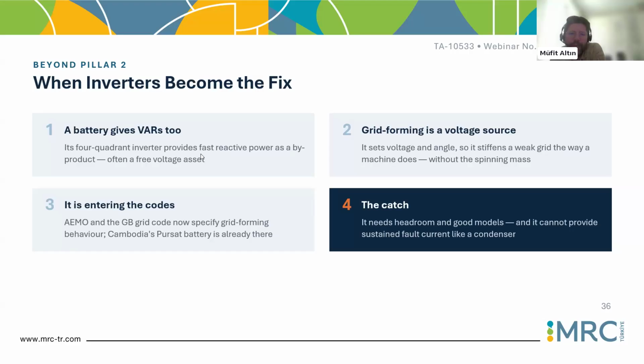Of course, the idea of grid forming is that you have a voltage magnitude and angle, and you would like to control them like a voltage source. But when you have a converter, you have limited capacity. You cannot exceed the converter's overload current capacity and also its maximum voltage capacity, unlike synchronous condensers or synchronous machines. But it's a solution you can use after the analysis. Then for weak grids, you can improve.